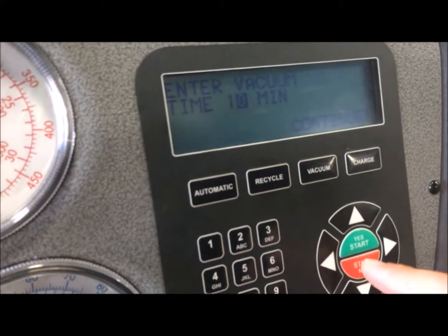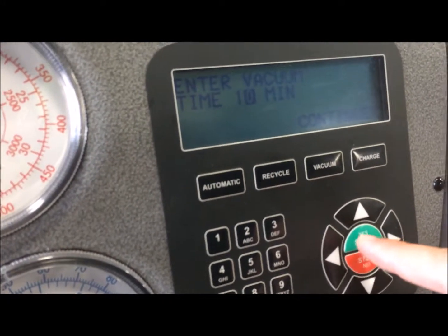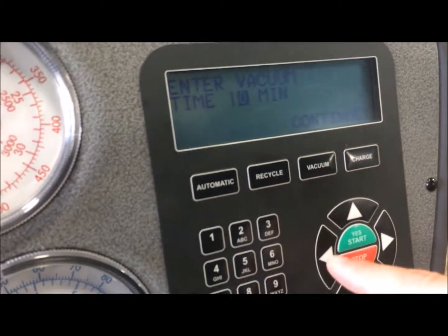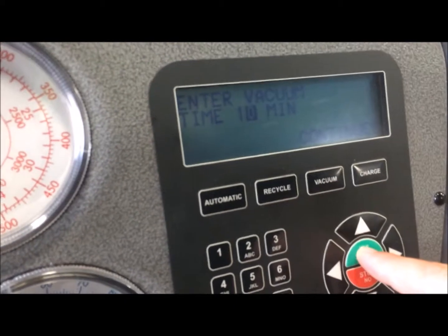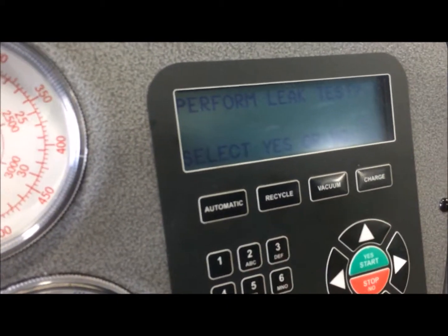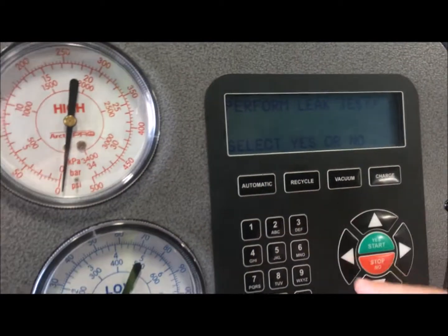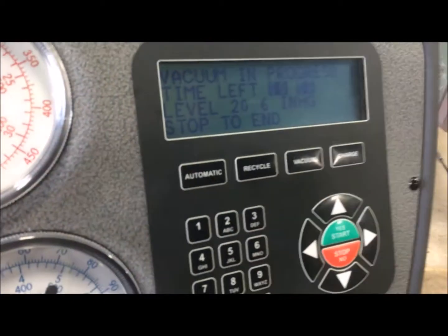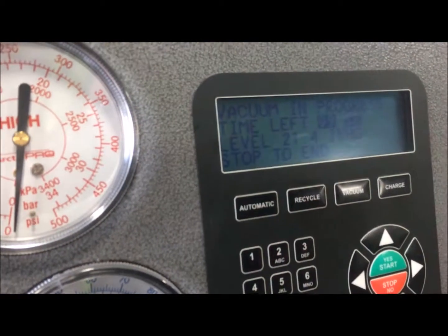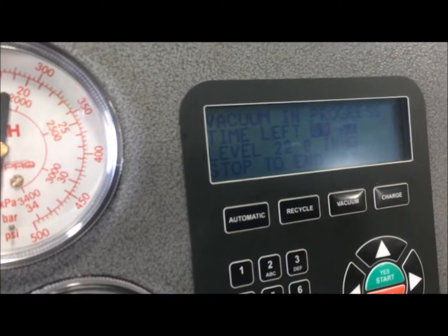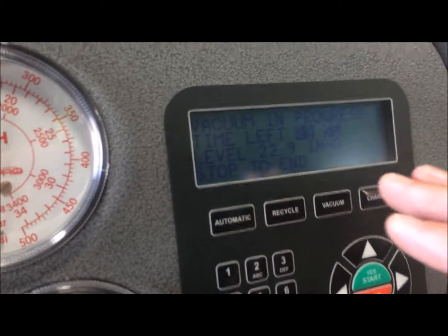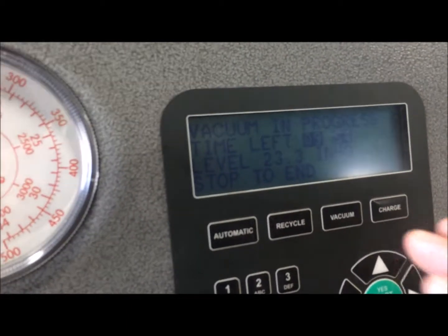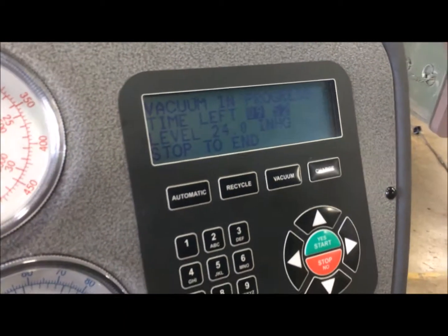Vacuum time. We're going to do a vacuum for 10 minutes. Now, after the 10 minutes is up, we want to go ahead and let it sit for 5 minutes for the leak test.